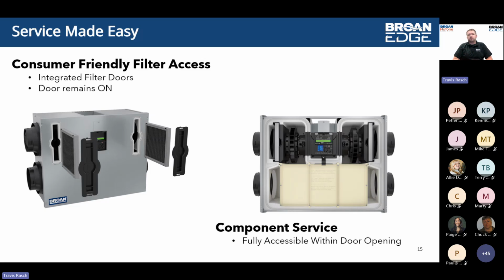If and when you do have to get into the rest of the components, meaning the recovery core, the blower fan motors, the electronic assembly, or anything else that would need to be serviced, there are fasteners along the perimeter of the door panel, as well as 2 fasteners around the screen. If you have a hardwired model, there is a fastener for that access panel as well. You remove those, and then the steel panel as well as the insulation panel get pulled off directly, and you can get full access to anything you would possibly need within that opening, and adequately service the product from within that door opening.